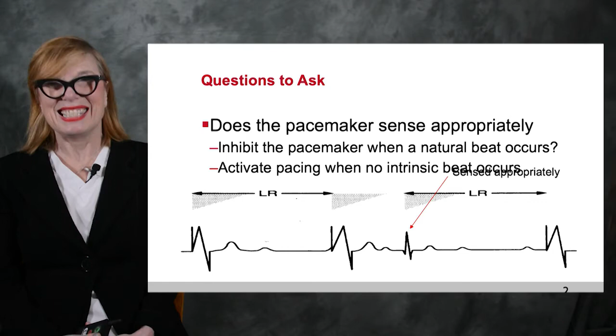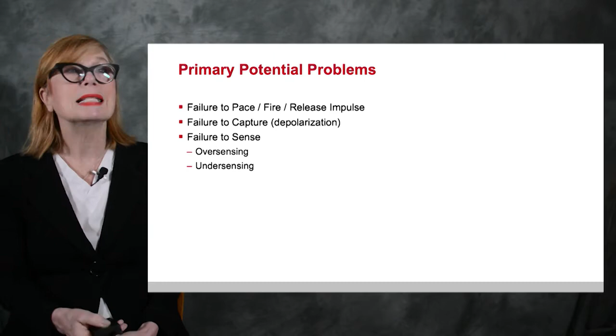So the primary problems that we're going to consider for our application, which is very generic here, of pacemakers, are failure to pace, meaning no impulse is fired and there's no reason for it not to have. Failure to capture, which means the impulse is fired but there isn't a responding depolarization. And failure to sense, meaning you're sensing too frequently, not a real beat, or undersensing, meaning you're not sensing frequently enough. So let's take a look at a couple of those strips.